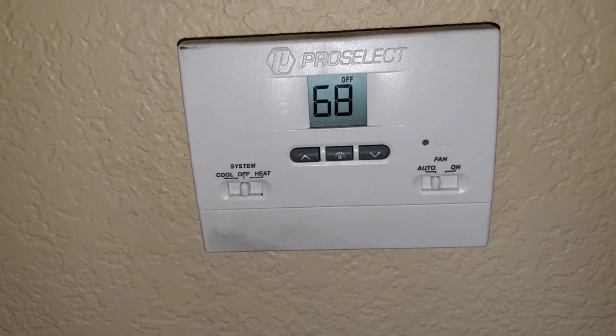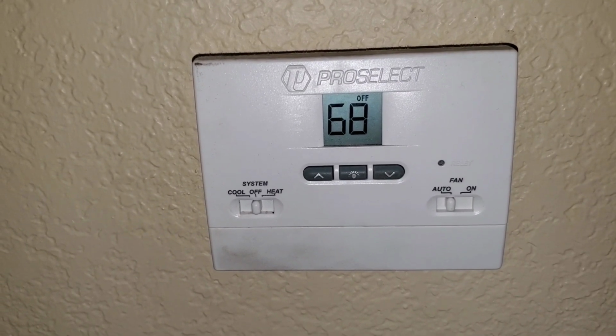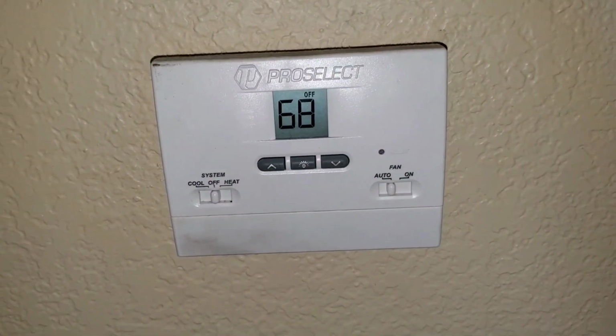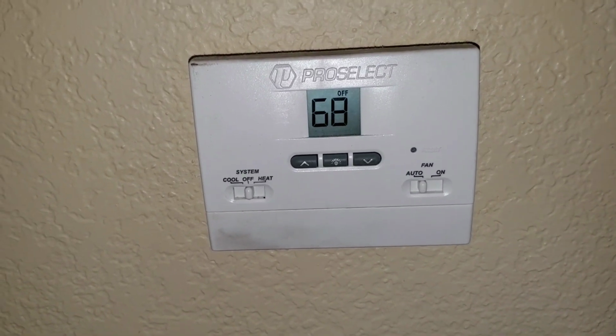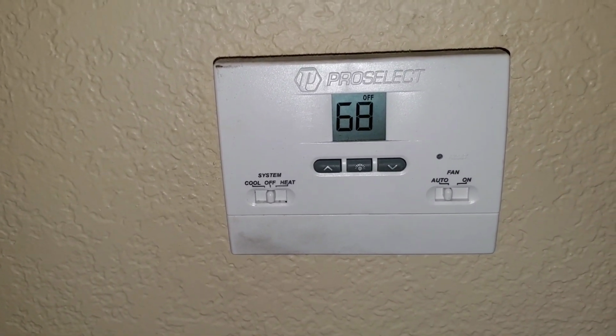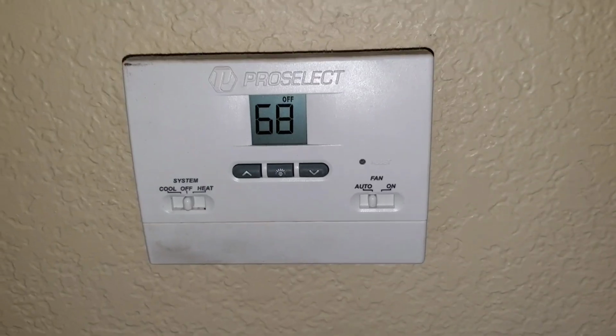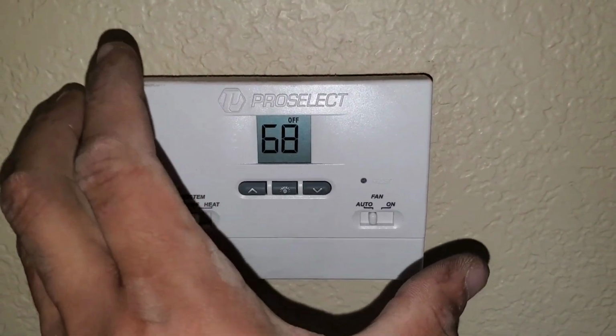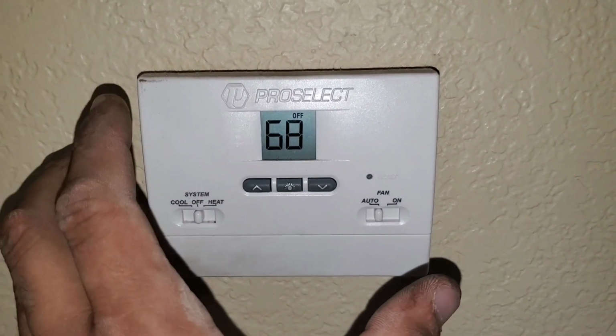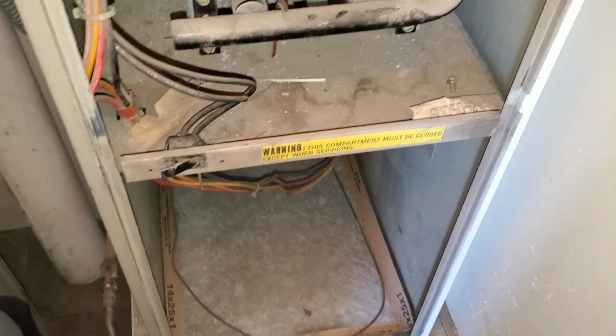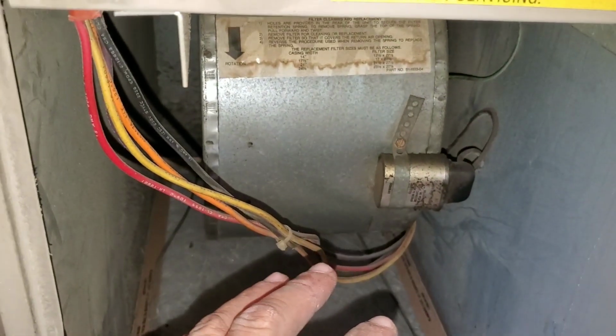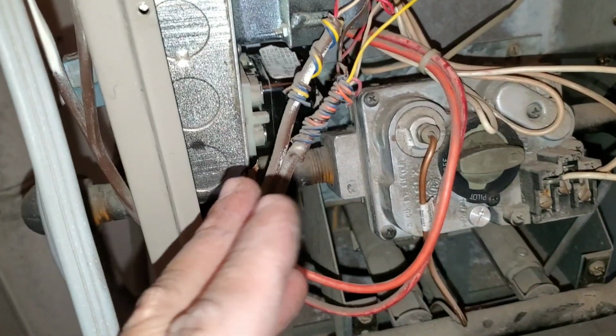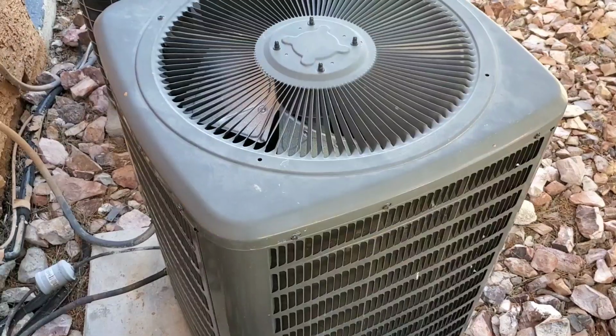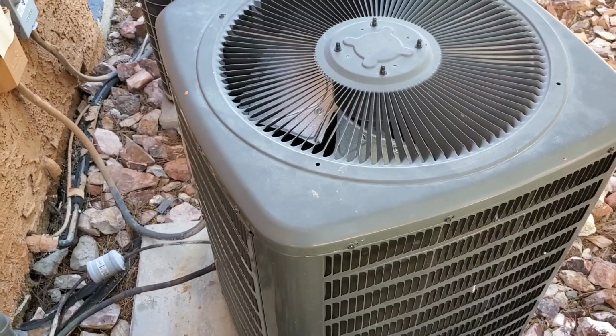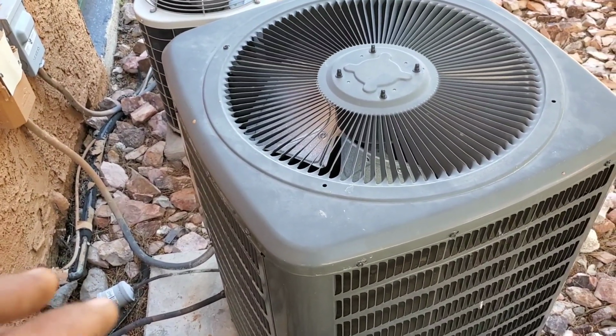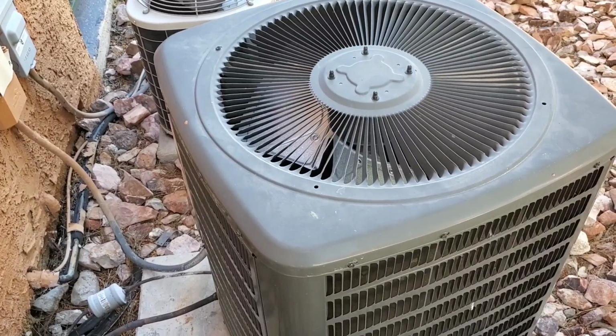Part one, we basically just wanted ourselves to get a visual and mental understanding of how our system operates. What you're trying to do when you're working on your AC system is mentally and visually separate the system into three parts. Obviously, you want to start at the thermostat. That is part one of your mental visual understanding of how your system works. The second part is going to be your return. This is where your blower is, and where your transformer, your relays, or your board may be. Your condenser is going to be part three, just allowing yourself in your mind to isolate and separate when you're doing troubleshooting to your HVAC system.